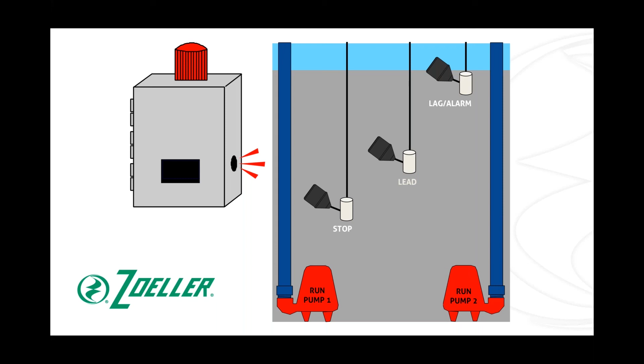drop. The lag/alarm float switch has dropped out. Our audible and visible indicators on the control panel have been deactivated. Both pumps continue to run. And right now our lead float has dropped out, but both pumps stay running all the way until the stop float drops out and we are back to a normal water level and we are ready for the next pumping cycle. So that's just kind of the operation of a 3-float duplex control panel.